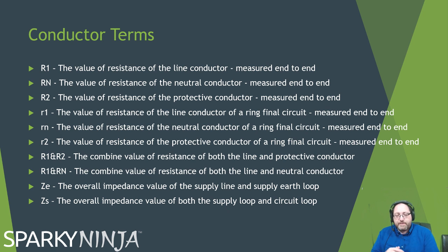The ZS is the supply loop of ZE plus the internal loop of your circuit of R1 plus R2. So you may have heard that formula before. The ZS is equal to the ZE plus the R1 plus R2. The total loop is the overall value of the external plus the internal loop. Okay, you'll see these units popping up a few times in all testing and inspection courses. It's one of the building blocks of these courses, really. It's your knowledge on units.